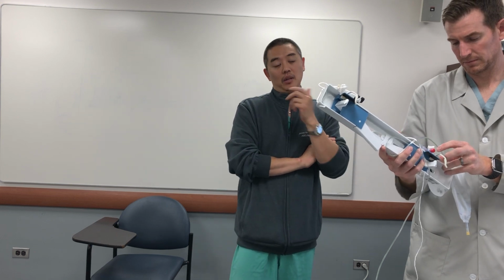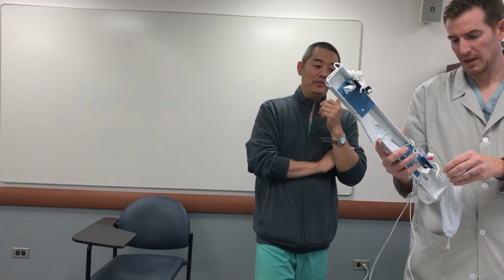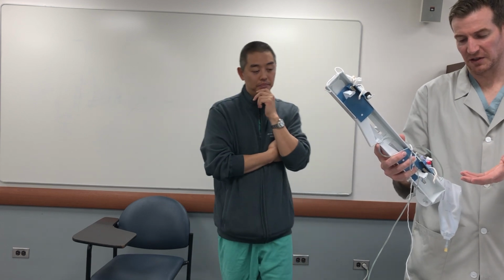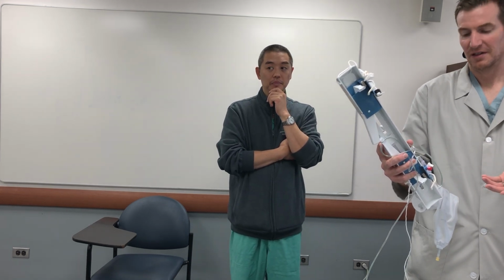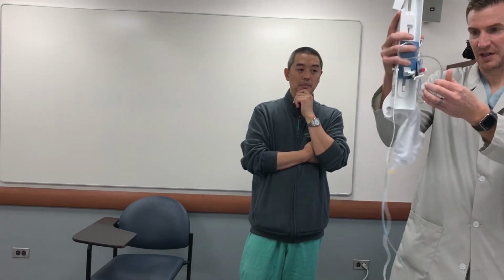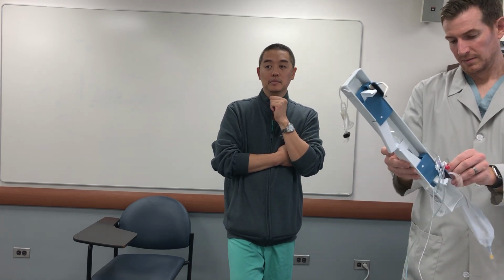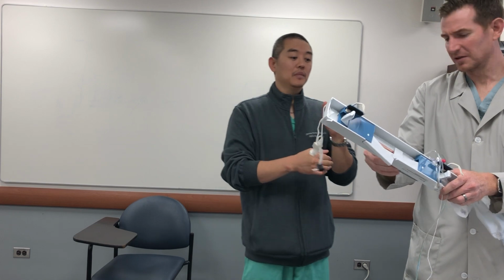Yeah, but you have to lower it and have it all at zero, technically. Technically, but if you're just zeroing the transducer, it's just to atmospheric pressure. So you have this off to the patient, whether you're here or here. No, but what I'm saying is, usually I bring the patient down, get them in position, and put it level with the patient's ear. Then whatever the height was set at upstairs, if it's 15, 10, whatever, you clamp to the patient, lower that down to zero, hit zero on your monitor, and then raise it back up before you open it. Do you guys do that to zero? Do you guys put it down here?